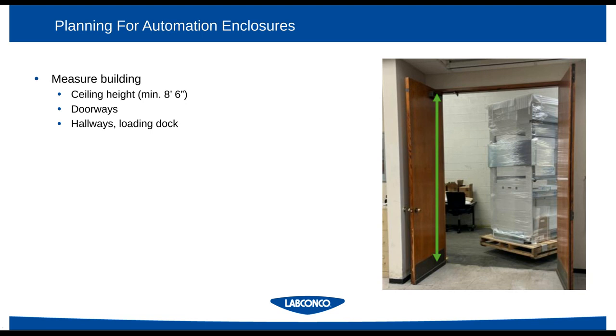Also, doorways and hallways and the loading dock, as I mentioned, are really important to evaluate. The Logic View can be stripped down to a much smaller size for passageway through standard doors, but at the same time, it's important to understand that before just receiving the equipment and pushing it straight into your lab. You may run into some challenges that require additional installation requirements.